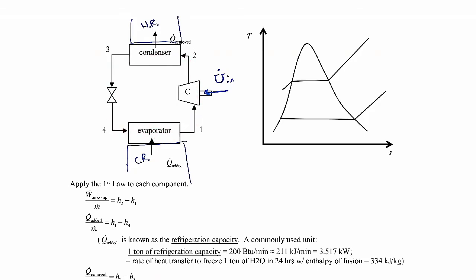If we sketch out the cycle on the TS diagram, state one is typically located right along the saturated vapor line. Moving through the compressor, we go to a higher pressure — a different isobar. At 100% isentropic efficiency we'd go to point 2s, but in reality we increase entropy a little and go to state two. Compressors operate best with pure vapor rather than a saturated vapor-liquid mixture, so we're typically operating in the superheated vapor region. The pressure at state two is greater than at state one. Then we go through the condenser to a saturated liquid state at constant pressure, giving us state three.